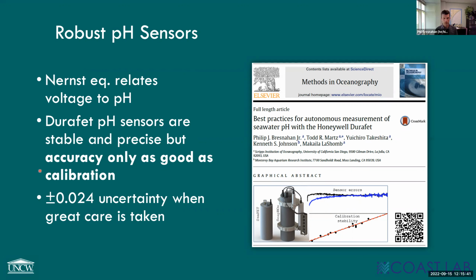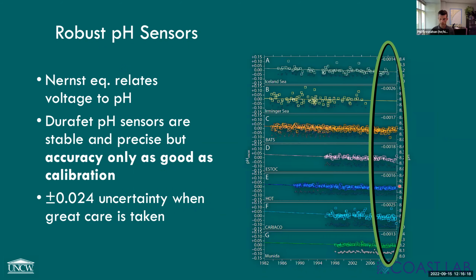And maybe that goes without saying for a lot of devices. We should always assume that there's a certain amount of calibration or at least validation required for our technology. But it's especially the case here. If you put an offset of 5 in, your pH will be off by 5 units. If you put an offset of 0.01, then you can really dial things in a little bit further. And what we learned through some of the early studies with these devices is that with a pretty good amount of technical care and attention, we could get down to about plus or minus 0.024 uncertainty. And remember, we're talking about this versus our rate of ocean acidification, which is an order of magnitude smaller than that. So in order to actually try to unravel what's happening in the global ocean over these decadal scales, we need something that's a lot more accurate than that.